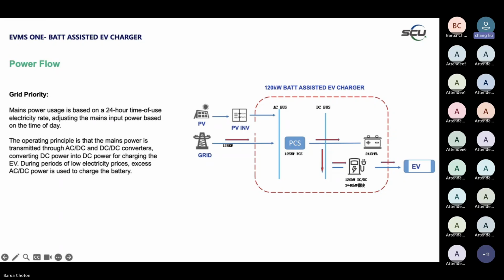Since battery capacity is 240 kilowatt hours, how long will it take to charge from solar only? It depends on the power you can provide from solar, but the maximum power to charge the battery is 125 kilowatt, because our PCS is 125 kilowatt. So if you're giving full power, it will take about 1 hour to get 125 kilowatt hours, then less than 2 hours to fully charge the battery. But practically you won't discharge the battery to 0%, so there will be some state of charge remaining, maybe 20% or 15%. We can swap between the grid and PV. I'll explain how the power flows.